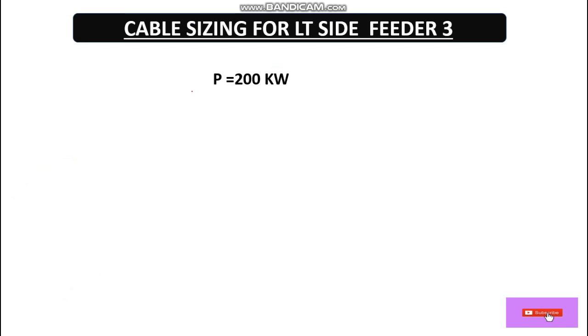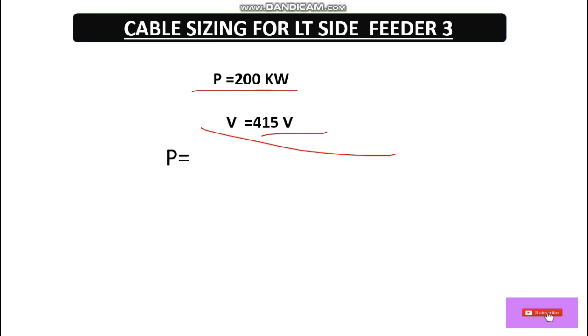For this 200 kilowatt load, the voltage is 415 volts three-phase. The formula is: P = √3 × V × I × cosφ, where V is the line voltage, I is the full load current, and cosφ is the power factor.